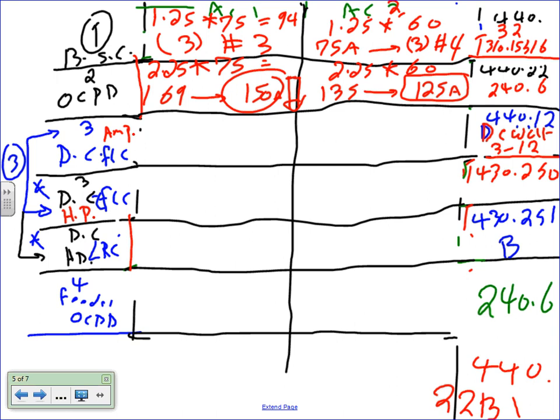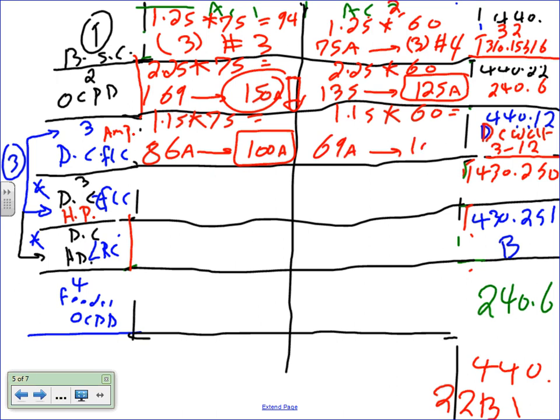Because of this, if you guys go to 440.12 and Table 312, you guys are familiar with this one. 1.15, that magic 1.15, multiplied, Chris, by the same 75. That will give me 86 amp, and this will translate into 100 amp from the table, and 1.15 again times 60. That will get me 69 amp, and that will translate also to a 100 amp disconnect. Both of them amp-wise will be sized as a disconnect.